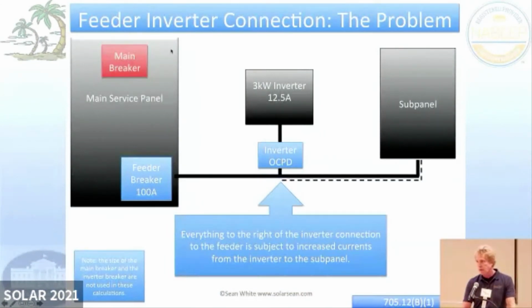So we talk about connecting to a feeder, but what we have here is what's called a feeder. And a feeder is going from the feeder breaker in the main service panel, or it could even just be one breaker going to the utility, but we're going to call that a feeder because there's overcurrent protection, and then it goes a long distance and goes to a sub panel. So let's call that the feeder. But we could also even kind of look at this as being the feeder. It depends on the way you look at it. You have to look at these things from different angles.